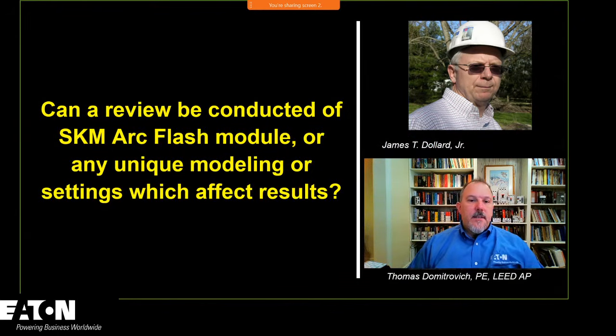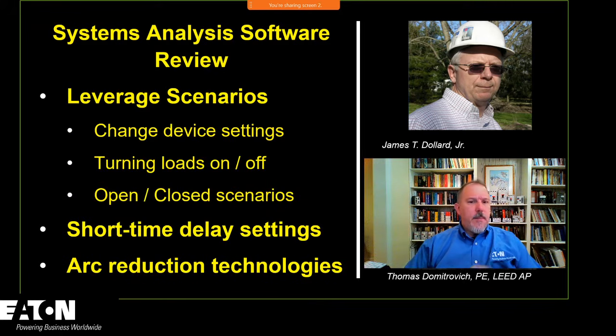Can a review be conducted of SKM Arc Flash module or any unique modeling or settings which affect results? So, in my opinion, from a power systems analysis software standpoint, this question called out SKM, and I'm sure that other software applications have the same capabilities. But in SKM, we can run scenarios.